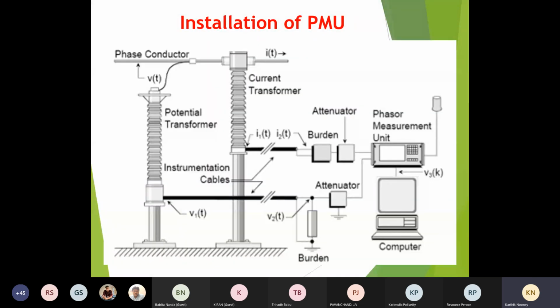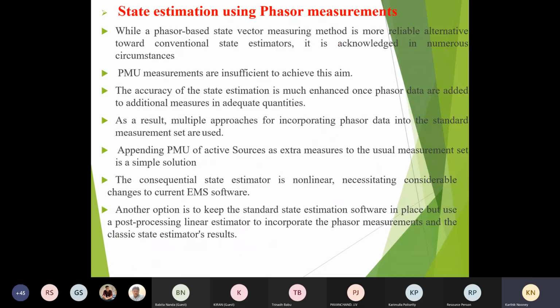Okay. This way the PMU is installed, as in the live diagram I have got. See, from the current transformer secondaries, from the PT and CT, all with the help of attenuators. That means they decrease those values, but decreasing does not mean they will bury the original values. Whatever is exactly required by the PMU, for that they will decrease, and any attenuator, if any spikes are there, will decrease those noises and give the signal to the phasor measurement unit. And at the top right hand side is indicated the modem, and it is linked with the computer.